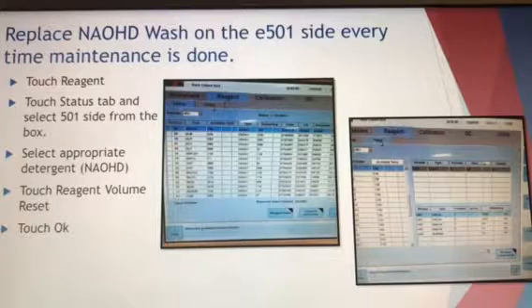While we're doing that, or after, you're going to make sure you replace your NaOH-D wash on the 501 side every single time the maintenance is done. So this is done for the daily and the weekly and the monthly. It's done every day, no matter what. The first thing you're going to do is touch that reagent tab. Make sure the status tab is selected, and select the appropriate detergent. The appropriate detergent for the NaOH-D is the very first one. And then at the bottom, you're going to touch reagent volume reset, and then OK. I'll move on to the next slide so you can see what they look like.